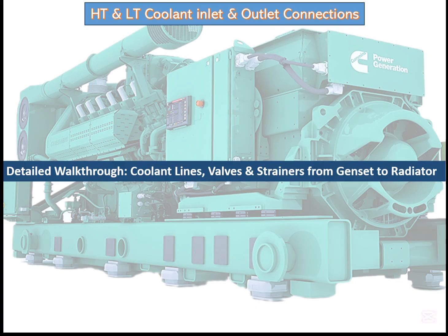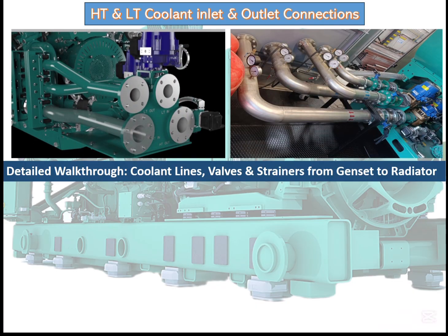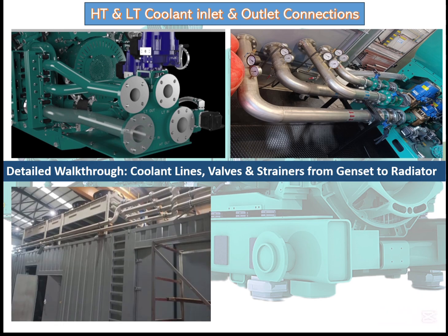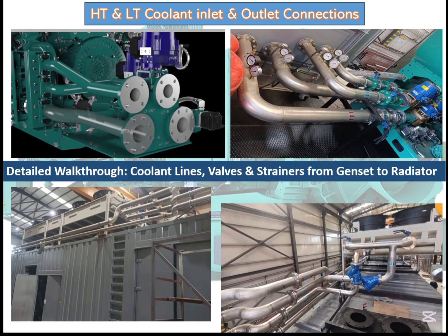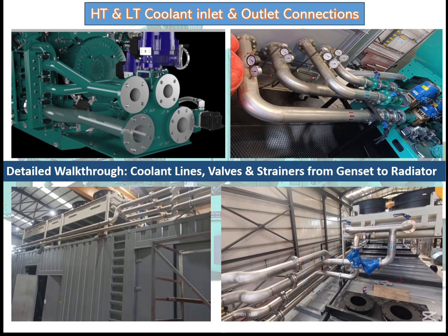Before we look at the cooling tower, let's look at the complete circuit from the engine to the cooling radiator, and how the pipes will run. This is the connection on the engine. We can put valves, standard pressure gauges and temperature gauges; we can see all of them in this picture. Then the pipe goes out to the height where we have our radiator. Here, finally, is where to connect the pipes to the radiator. I mentioned that the radiator has an inlet and outlet connection, where we bring lines from the generator to the radiator. We can install valves, standard pressure gauges and temperature gauges. This is the complete circuit from the genset connection to the radiator, showing how we lay the pipes and how we can arrange them.